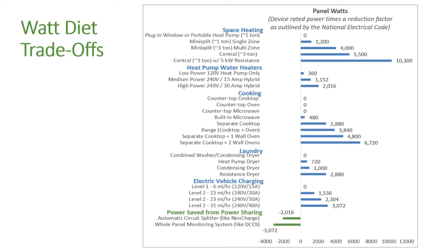The 0 is just plugging in that 110 or 120 volt EV charging cord that comes in the trunk of your EV — you open the trunk, get it out, plug it into the garage socket. It doesn't count on your electric panel sizing; that's just part of the general loading of the house, not a new counted thing.